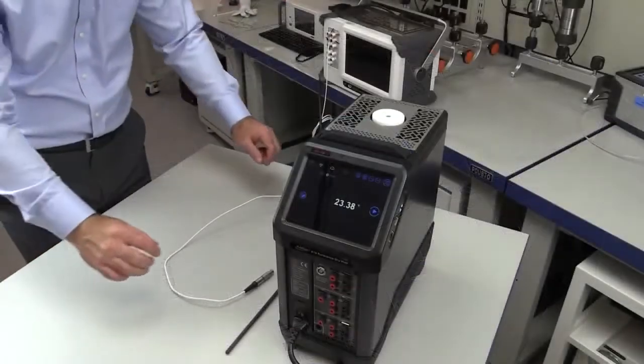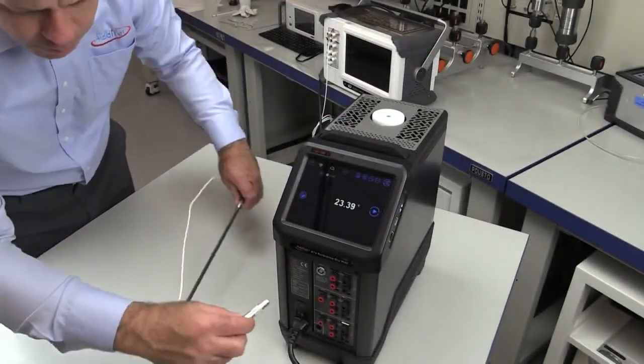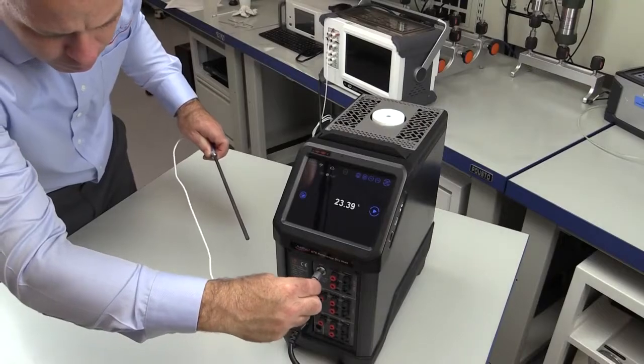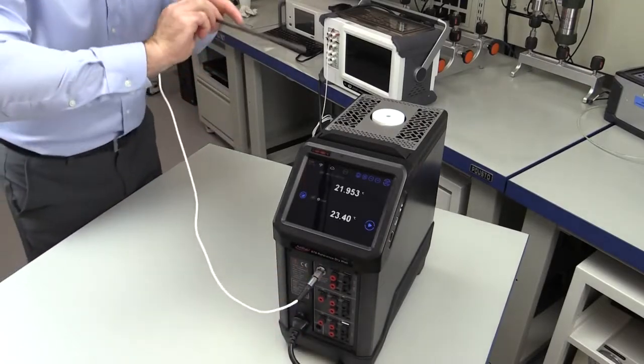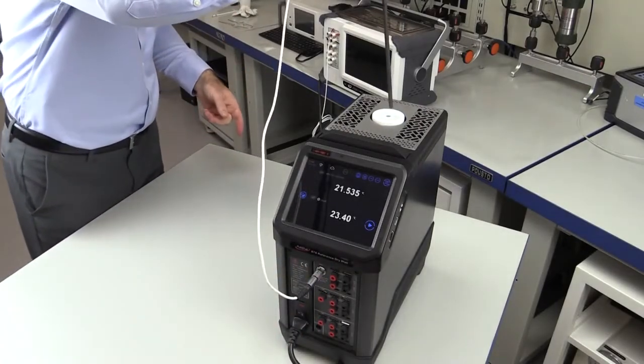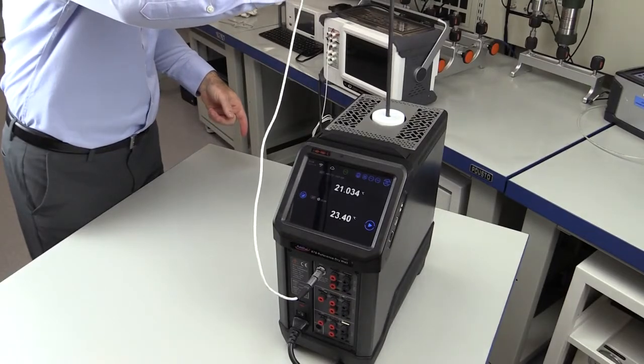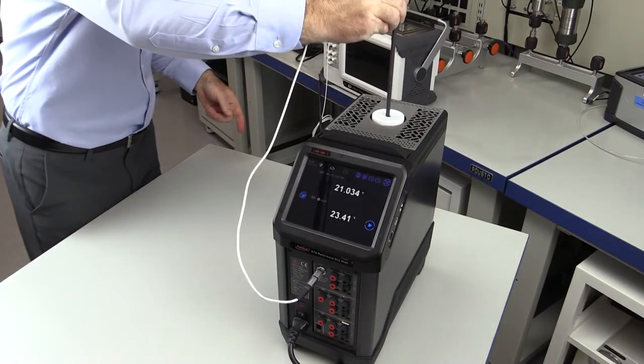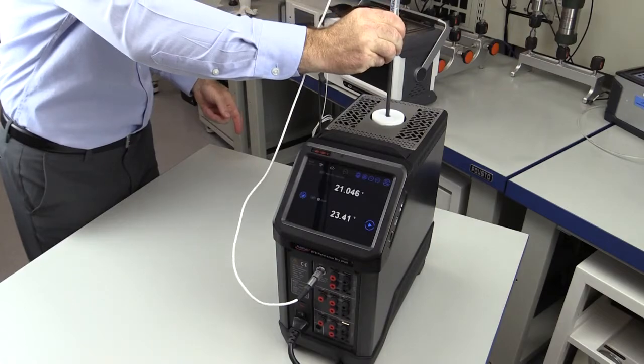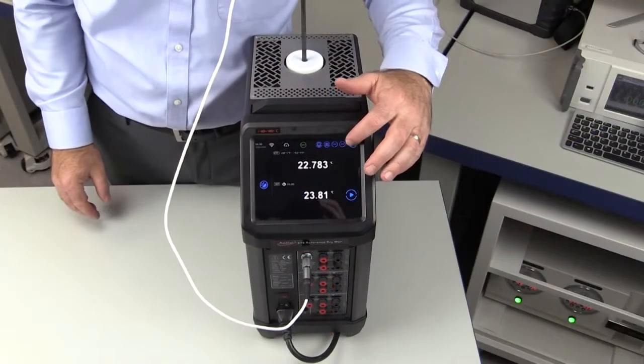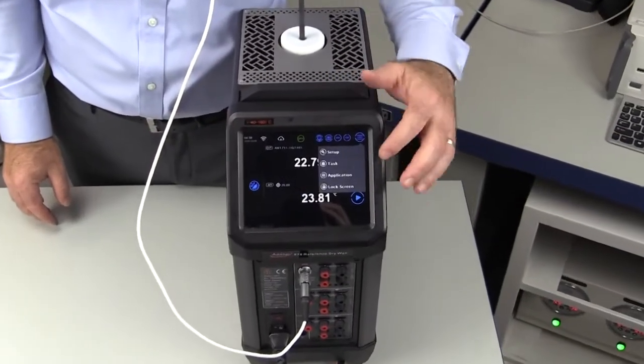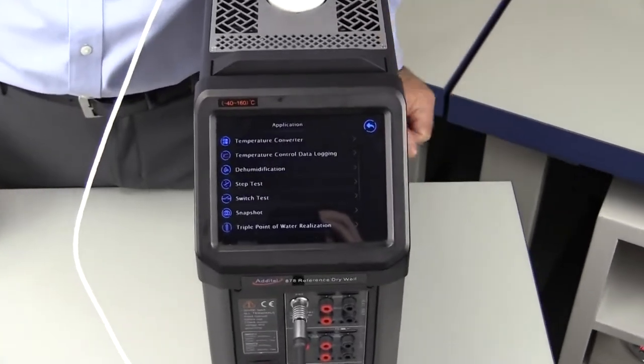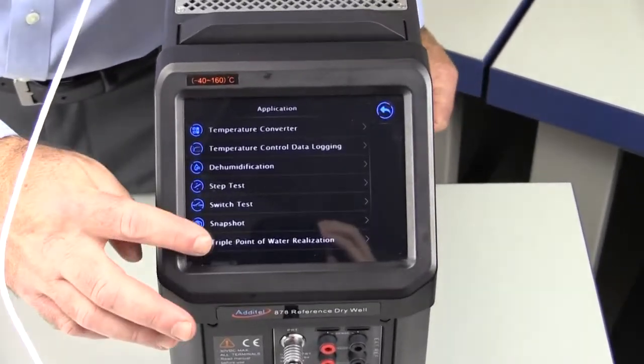The last step before running the automated built-in task feature is to insert the reference probe we wish to measure into the cell through the hole in the top of the lid. In this example, we are using the process calibration option of the ADT878, which allows for the reference probe to be read from the ADT878 itself. With a quick tap or two of the reference dry well touchscreen, we are off and running with our automated process.